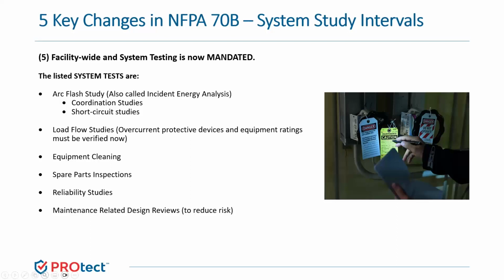It's important to note that each of these studies must be reviewed, verified, and potentially modified to align with the scope standard. Additionally, your single line diagrams used to calculate the short circuit values and protective device clearing times that ultimately determine the arc flash values and PPE requirements must also be reviewed and updated. So this requirement will be seen in the electrical maintenance plan.